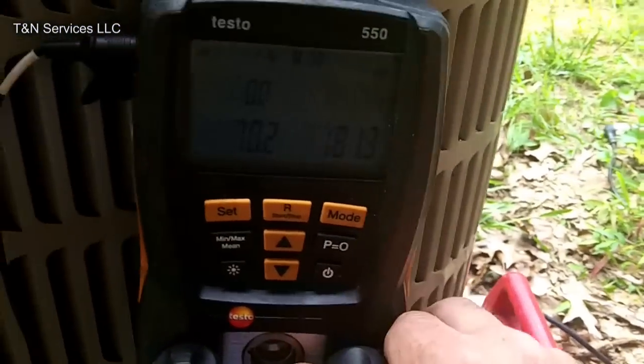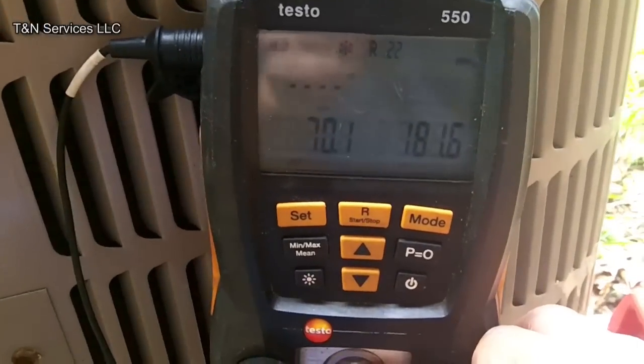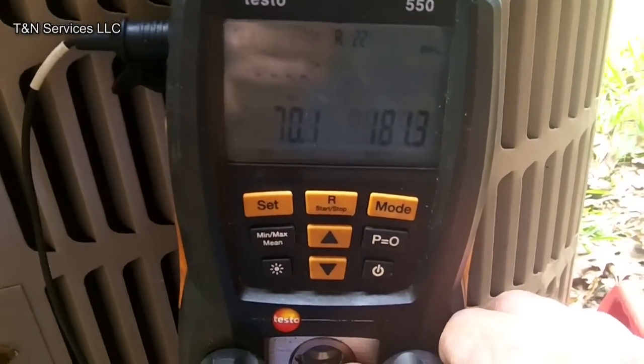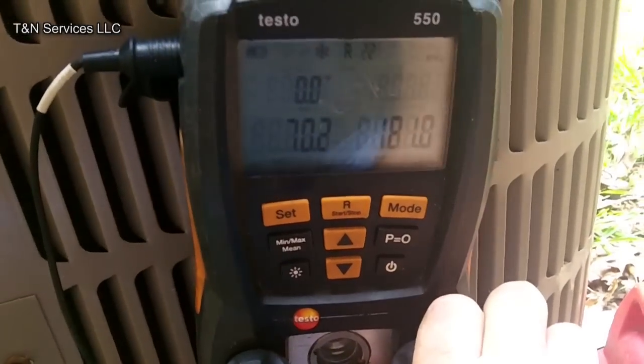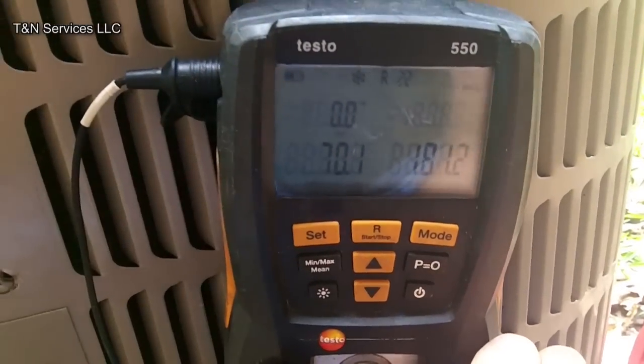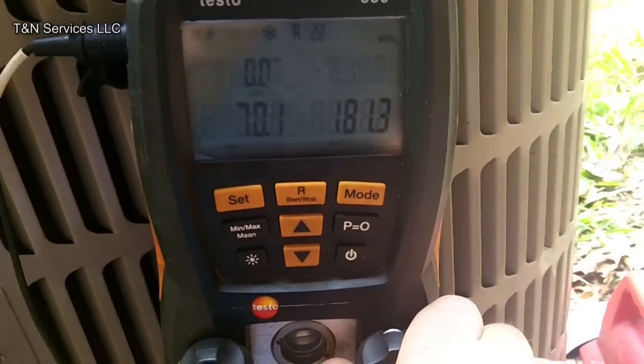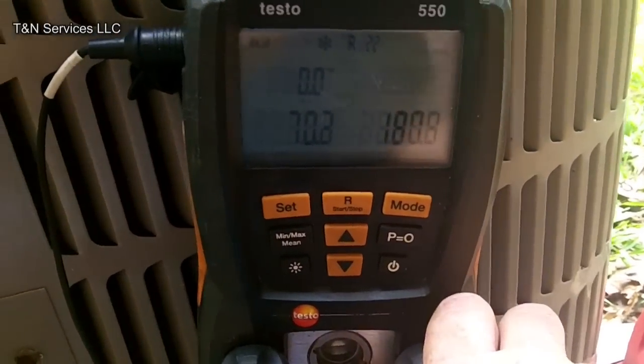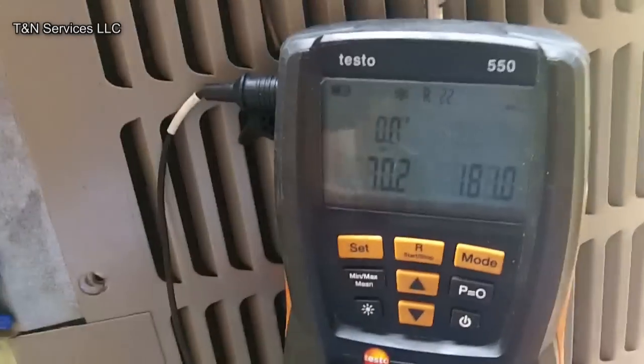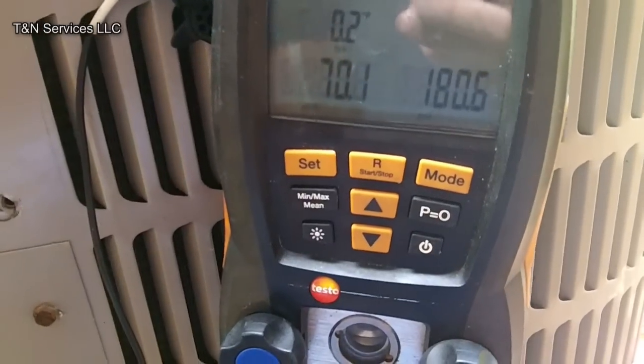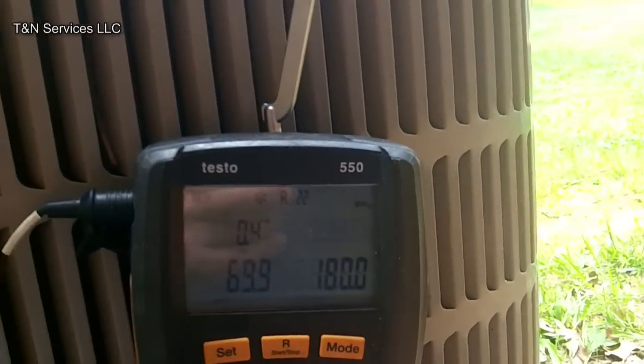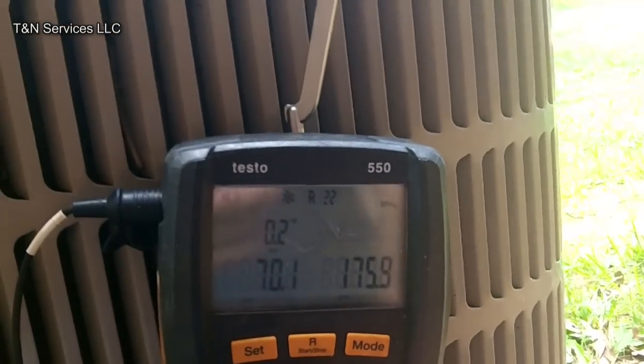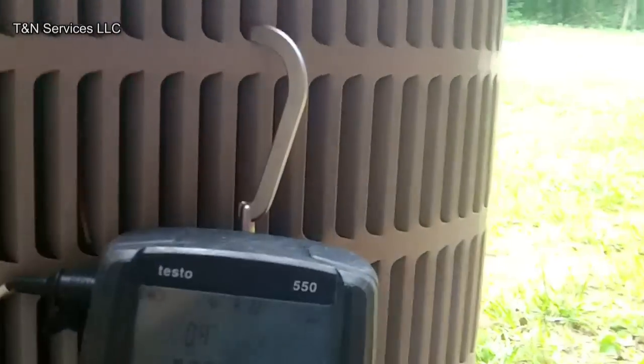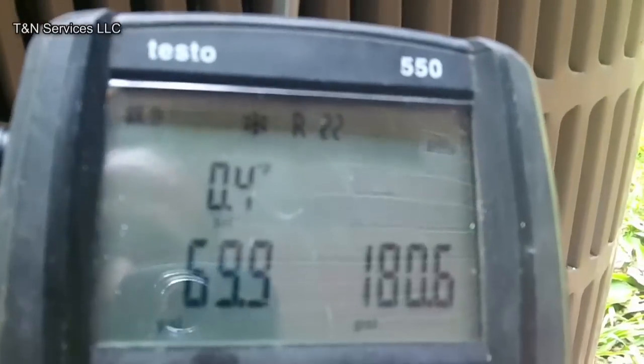So I've got my recovery cylinder out here. I'm going to start letting some Freon out of it, because it's about 74 in there now. I'm going to shoot for about a 65-pound suction and about a 15-degree superheat. But this system has some other issues on it, so I don't know if I'll be able to get my desired superheat because of the ductwork. This house was built in 1961, so we've got some ductwork issues along with it. So I probably won't get my desired superheat, but I will get it to where it's not zero.